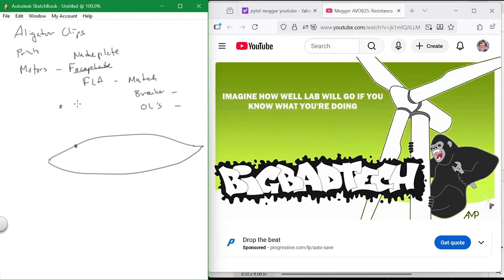This thing about the megger, that's a new megger. I didn't really know that that's what it was, but the old style meggers, you physically did this. I didn't do that. I would ask the electrician, "Have you meggered the motor yet?" They'll say, "Yes, sir. Yes, master. I've meggered the motor, and we're ready to go." But until they've done that, you cannot start that motor up. You cannot start it up until you got that question answered and checked off, or it'll blow up. Poof. You do not want that to happen.